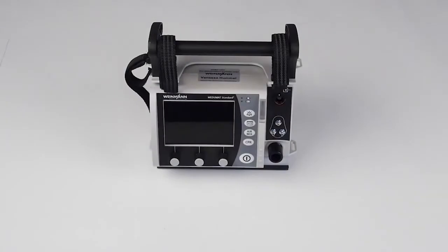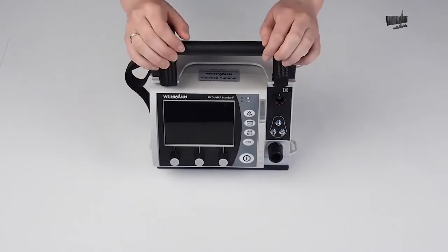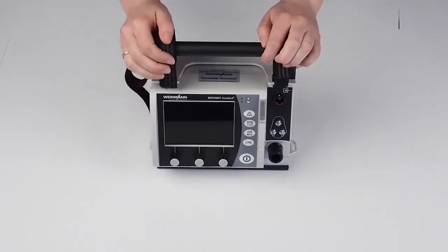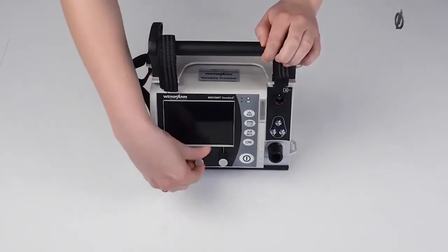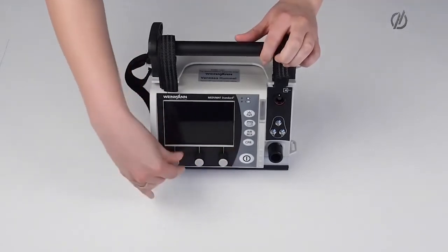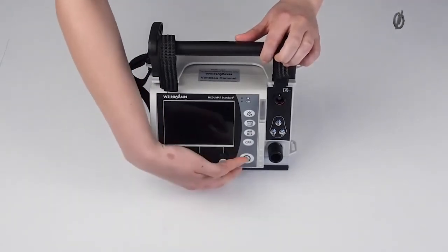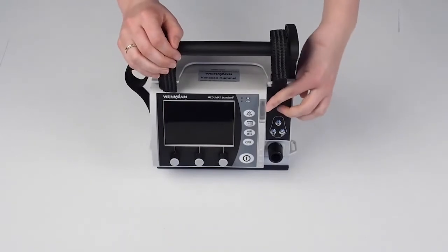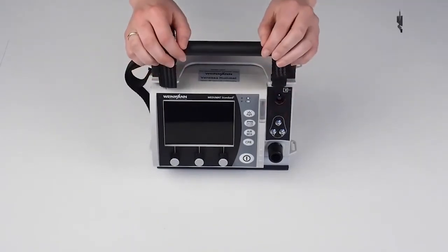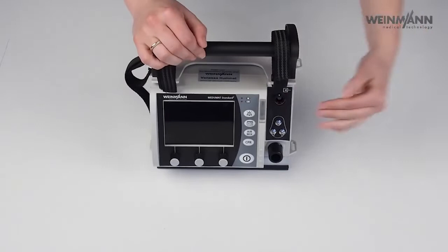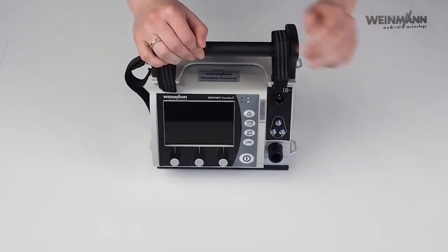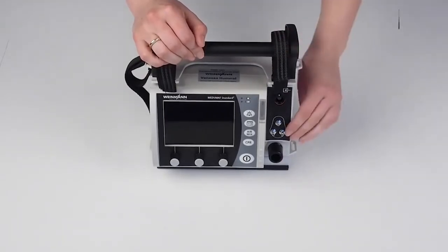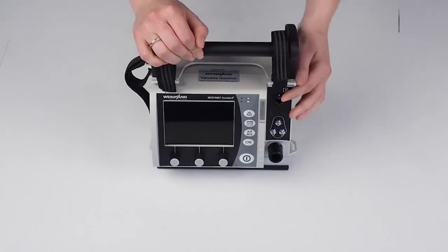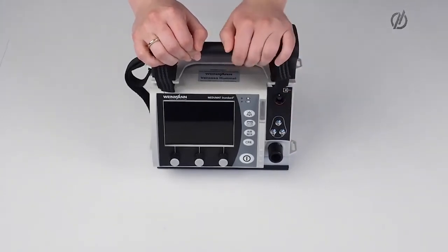So first, I would like to explain to you the outside of the device. To start with the front side, we have our display here, our rotary knobs with which you can make the settings. You can turn and click. You have the on and off button here, and you have the red alarm light flashing here in case of an alarm. On the left-hand side, we have our connectors for the patient hose system, for our measurement hose system, and for the flow measurement line.